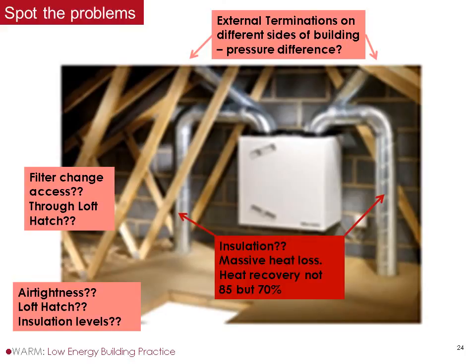But the big one is they haven't insulated the ducts. If you assume one of these is a modern unit with 85% heat recovery, say, I make that about 1.5 metres each side, that's 3 metres. We put it in our passive house calculator, and it says no, it's not 85% anymore, it's 70%. So a real issue, these.